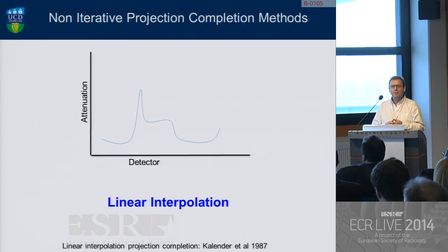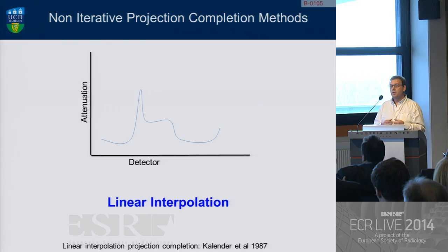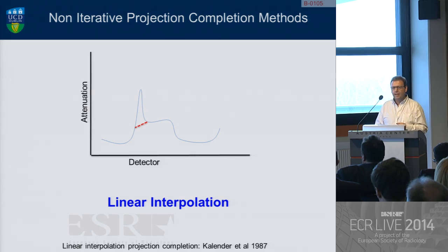There have been efforts made way back in the 1980s by Kalender. We saw linear interpolation being used to actually try and remove these defective measurements from the reconstruction. These techniques are still used a lot for the seeding images when we use iterative reconstruction. Basically, the idea is that we identify the metal within the scan field, look at those projections within the sinogram, and we simply average them out or get rid of the defective information.